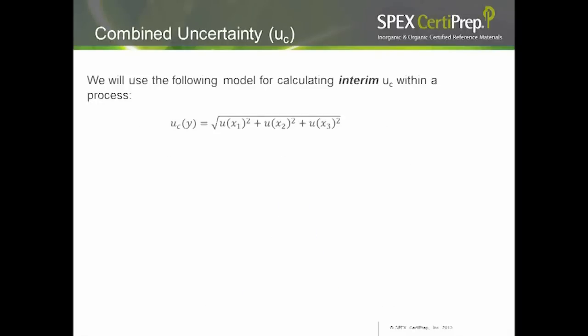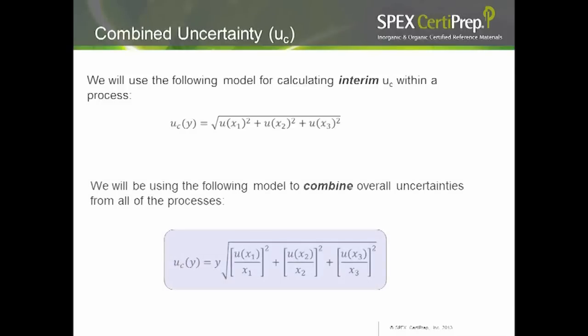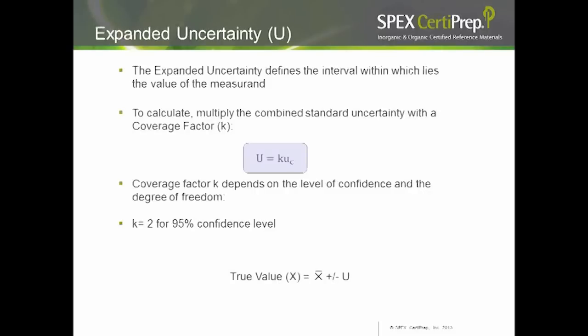Once you've normalized your uncertainty for each process, you calculate an interim uncertainty, then combine all interim uncertainties using a combination formula to get a total uncertainty. From that total uncertainty, you apply a coverage factor to get your expanded uncertainty. The coverage factor is determined by your confidence limit. For our CRMs, we use a 95% confidence limit, so the coverage factor equals two.